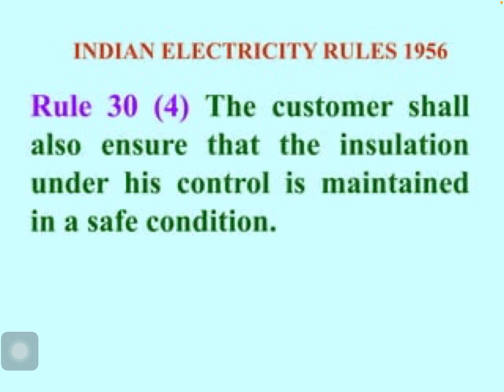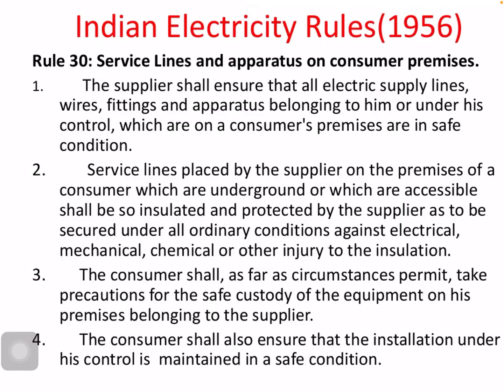Rule 30 talks about the customer: the installation which is under his control in his premises, he should ensure that the wires, fittings and apparatus belonging to him, under his control, should be in safe condition in all respects. The second point is the service lines placed by the supplier in the consumer premises, if underground, in ordinary conditions, be it in the mechanical, chemical or electrical way, should be properly insulated. And it also says that in any circumstances, all the apparatus of the consumer and of the supplier on the premises should be in safe condition. This is rule 30.